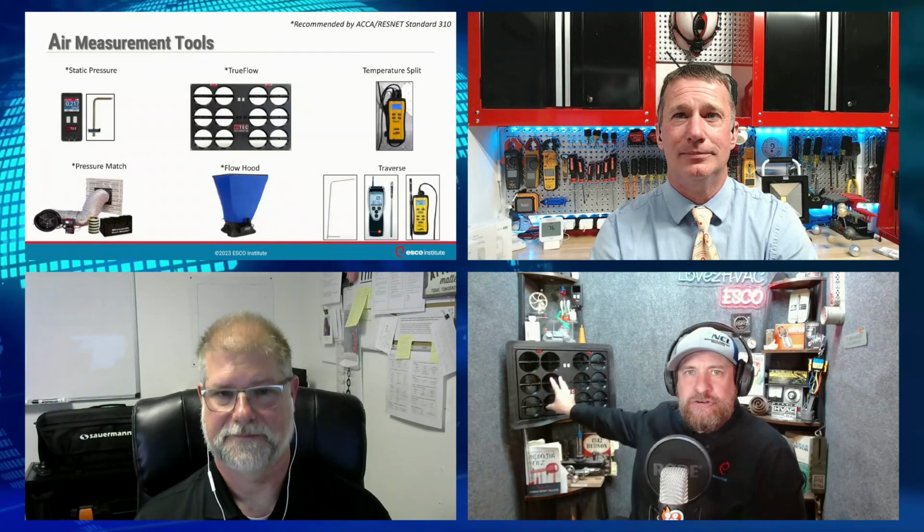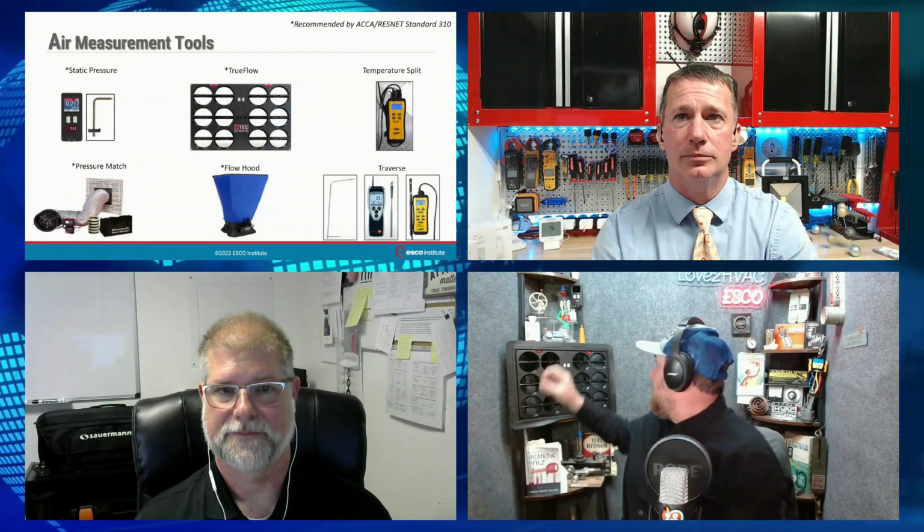And the True Flow Grid has an app that goes through it, with a small manometer that's very, very precise. It says, do this step here, get these numbers. What do you get? And then it does the calculations for us. Whether you're an experienced tech that's been doing it for 50 years or you're new to it, it leads you through these steps and very accurately gets those readings. Whether it's a new person, a salesperson, or somebody with 50 years of experience, it gets you these numbers, and then these numbers can be shared with the homeowner. Hey, here's how your system's performing right now.